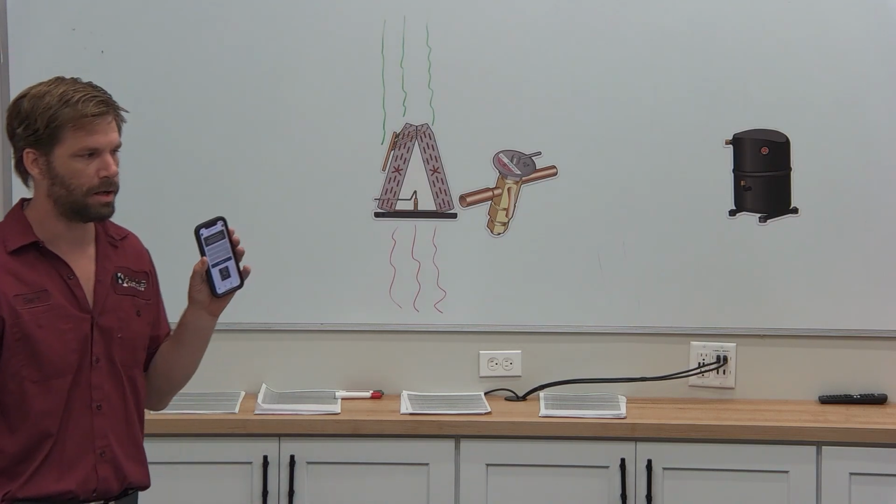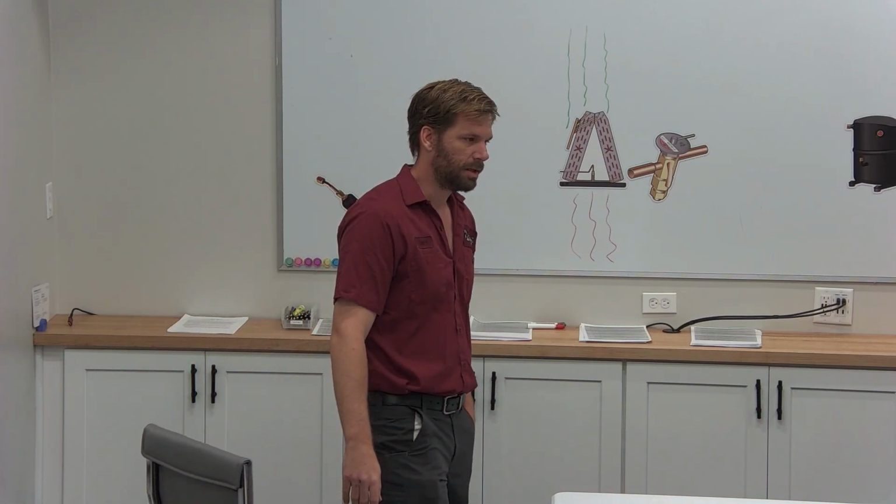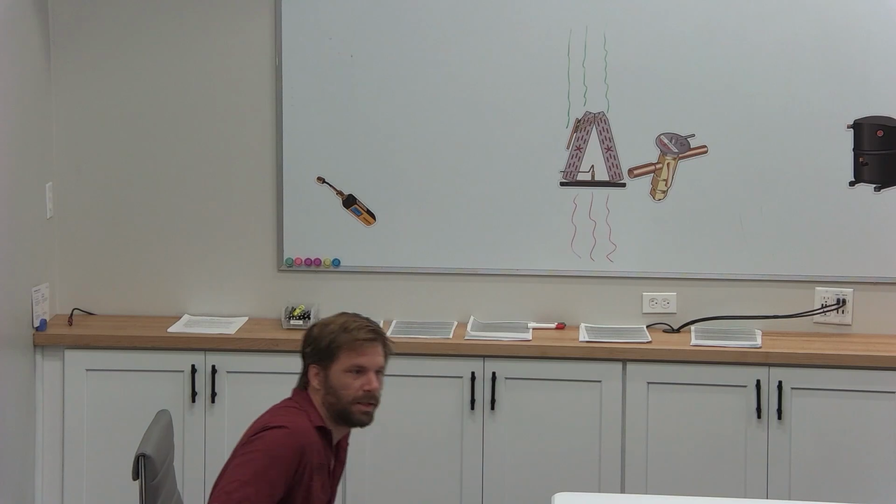If you use this a lot on systems that are performing great with 20-degree split, and this thing gives you a 19 every time you see 21, then you'll start to understand a little bit of the difference between the 400 CFM that this is set up for, and the fact that all of Florida is designed for the 350 CFM per ton. So that can help you understand where that slight difference will be. Also in measureQuick, you can literally enter that your airflow is 350 per ton, and then that'll calculate the split. So, if there's anybody still using measureQuick.